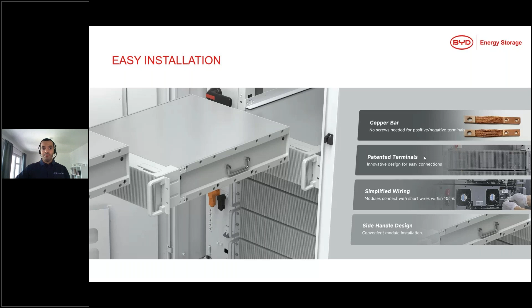And there's one highlight which sets the Max Lite apart from other C&I solutions, which is the high power rating. The Max Lite has a C rate of 1. That means that, for example, a 90 kilowatt hour battery has a power of 90 kilowatts. So it could be charged and discharged fully in just 1 hour. And again, that is very powerful. If you compare with other C&I batteries in the market, most of them have 0.5 or 0.25 C, but the Max Lite has 1 C, which again is very powerful. But you have to pay attention, because that's just the battery. You have to make sure that you combine it with the right inverter, because maybe the inverter is the power bottleneck. But again, it gives you some flexibility.